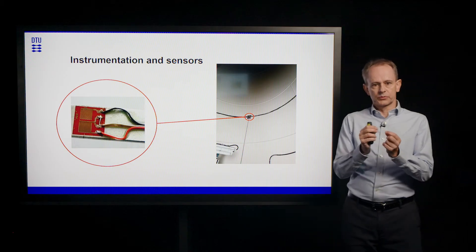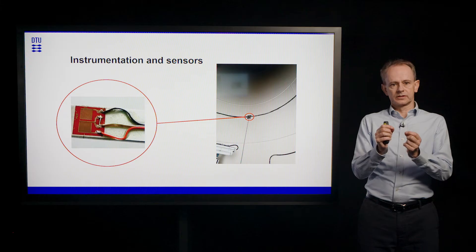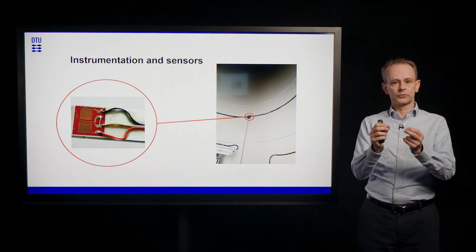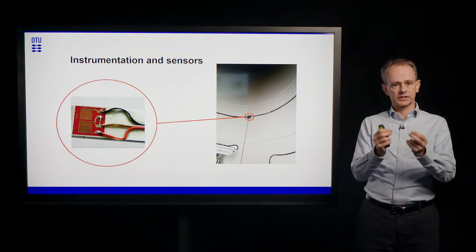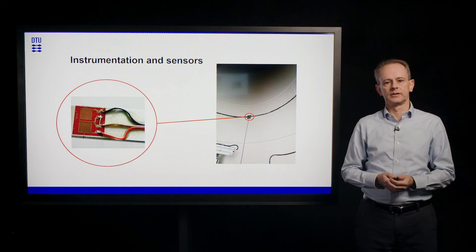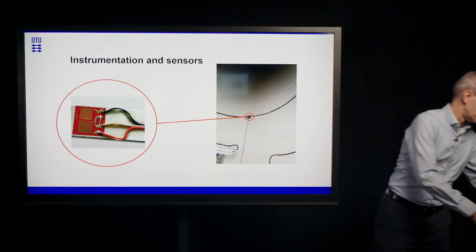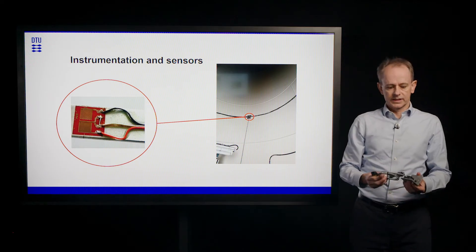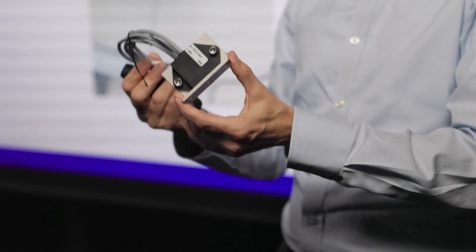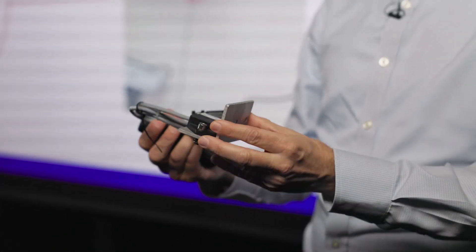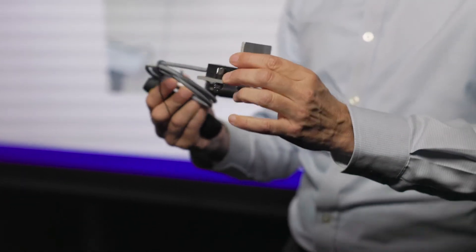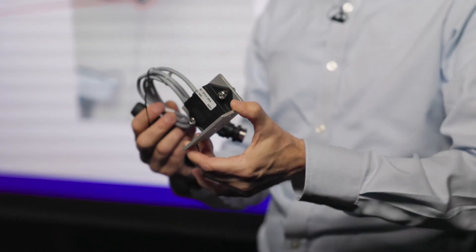By measuring the strain in the surface of the component, we can measure how the loading is. And through a calibration, we can calibrate the measured strain into a sectional load on the turbine. Another device for measuring response on a turbine is an accelerometer. And I have an example here. This device can be mounted on many different types of components and it measures the acceleration that this component is subject to.